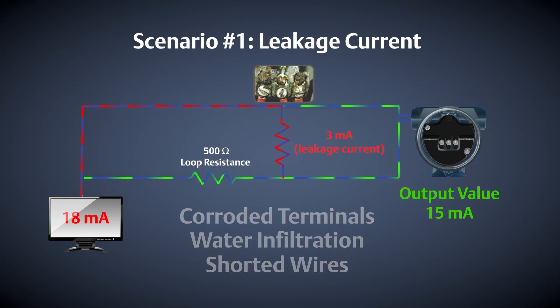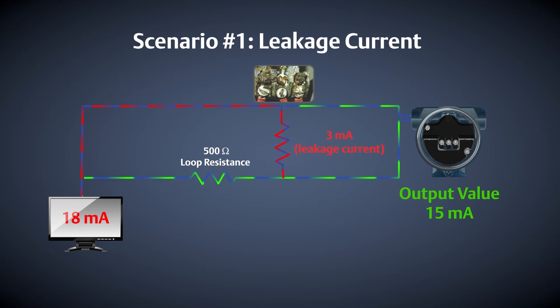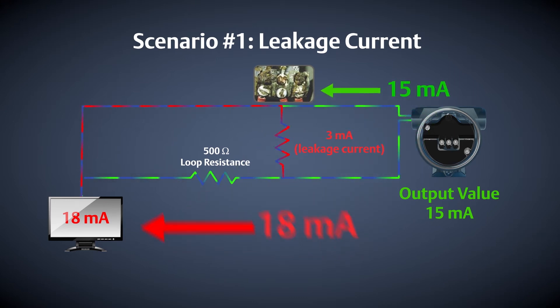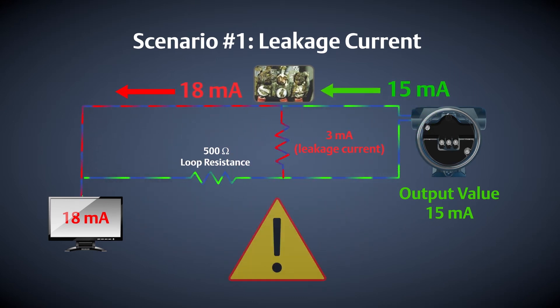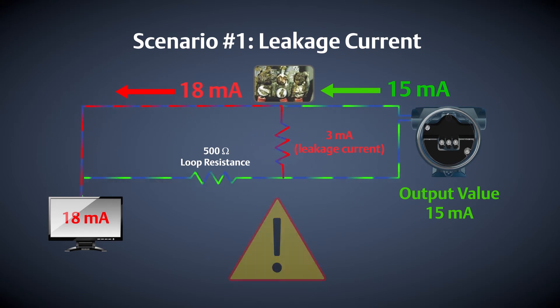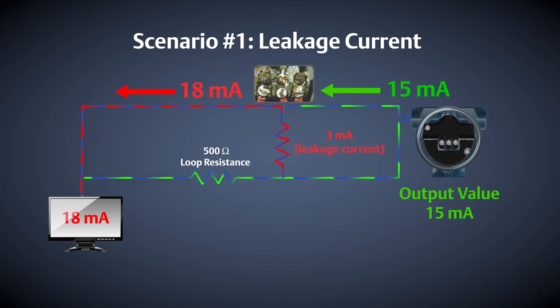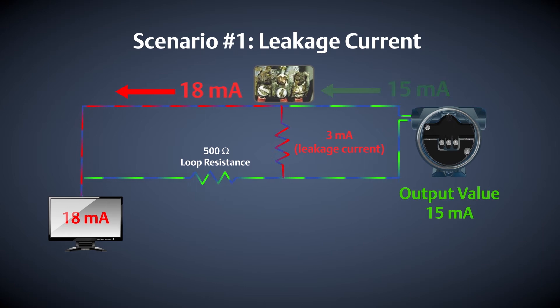Let's assume that leakage current has been created due to one of those factors. This additional electrical path causes a discrepancy between what the transmitter is outputting and what the control system is receiving, resulting in an on-scale failure condition where you could be taking control action on bad information. In this example, the control room is reading 18 milliamps even though the transmitter is outputting 15 milliamps.